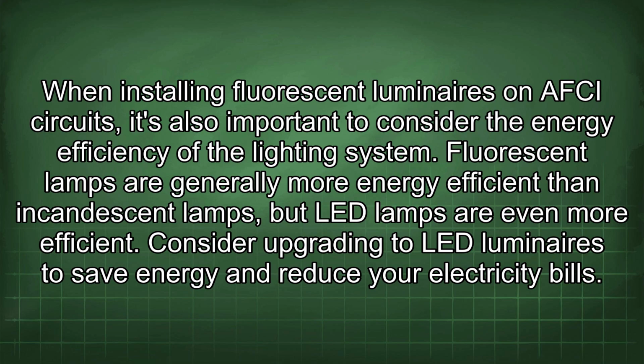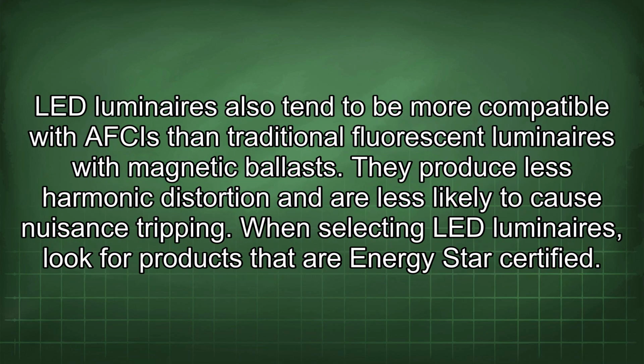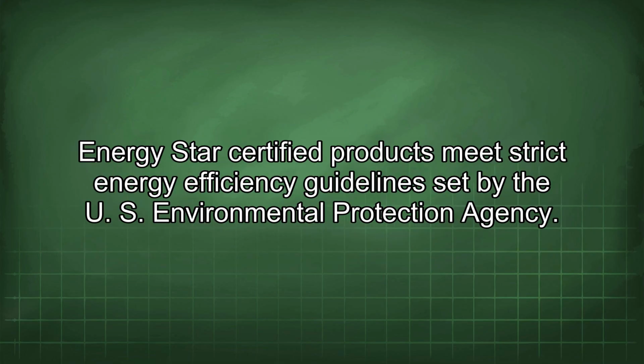system. Fluorescent lamps are generally more energy efficient than incandescent lamps, but LED lamps are even more efficient. Consider upgrading to LED luminaires to save energy and reduce your electricity bills. LED luminaires also tend to be more compatible with AFCIs than traditional fluorescent luminaires with magnetic ballasts. They produce less harmonic distortion and are less likely to cause nuisance tripping. When selecting LED luminaires, look for products that are Energy Star certified. Energy Star certified products meet strict energy efficiency guidelines set by the U.S.